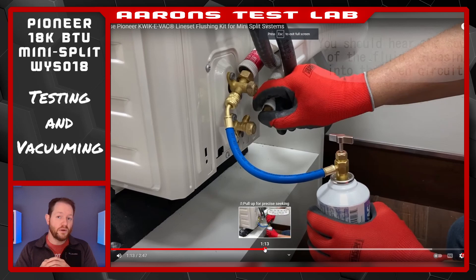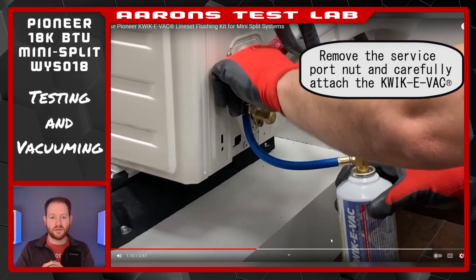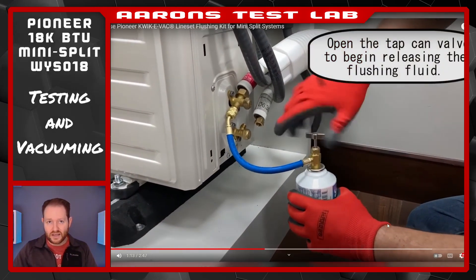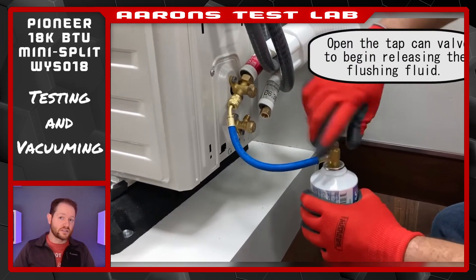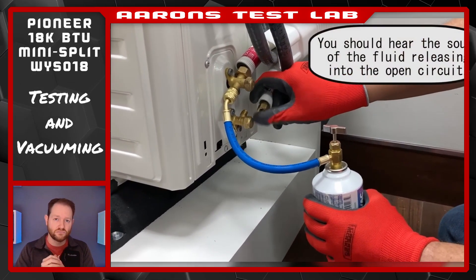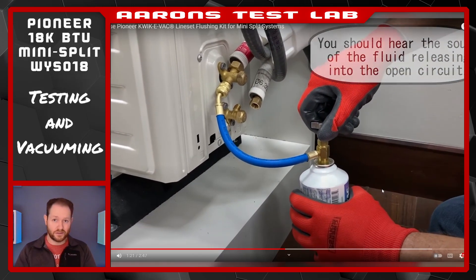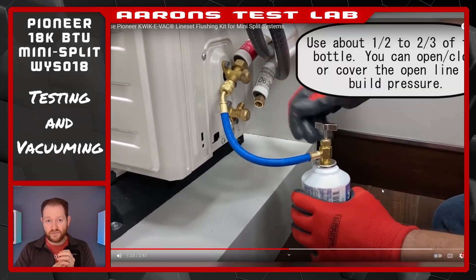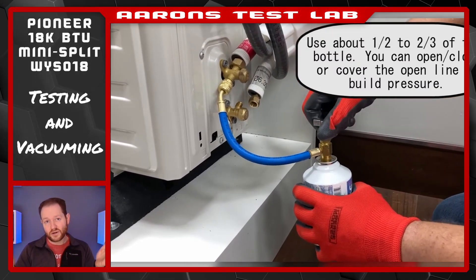Some of you might be wondering if there's an alternative to pressure testing and vacuuming if you're willing to accept a little more risk. The manufacturer actually endorses flushing the lines with a product they sell called KWIK-E-VAC. Instead of pulling air out of the lines, it replaces the air with something else. If you've got faith in your flare connections and don't want to buy a vacuum pump, give it a try. It's not for me, but I thought I'd at least point out its existence.